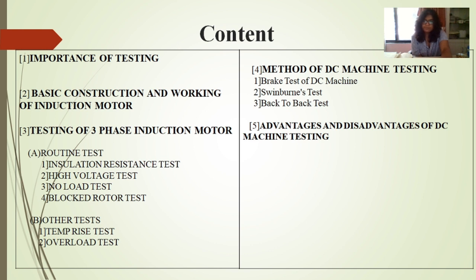So this is the content. First, we'll be learning about the importance of testing. Second, we'll be learning about the basic construction and working of an induction motor. Third will be the testing of induction motor, in which there is a routine test and other tests. In routine tests, there are insulation resistance test, high voltage test, no load test, and blocked rotor test. And the rest are the temperature test and overload test. The fourth will be the method of DC machine testing.